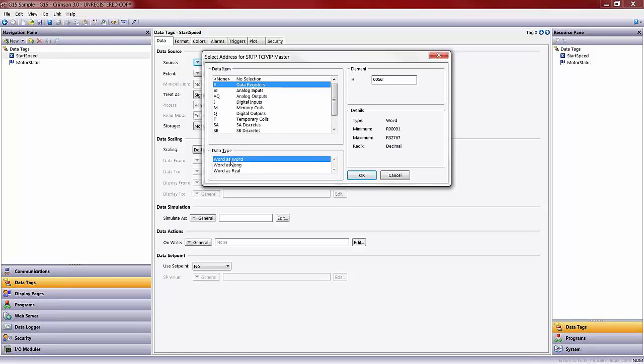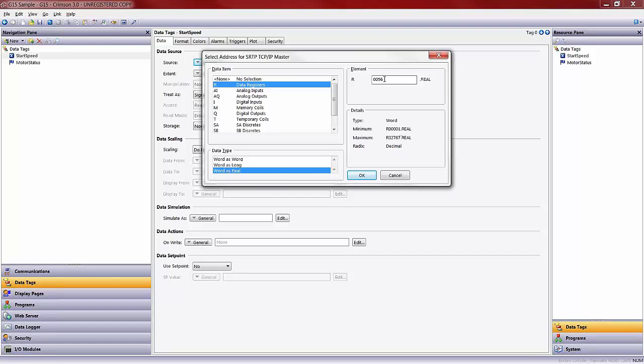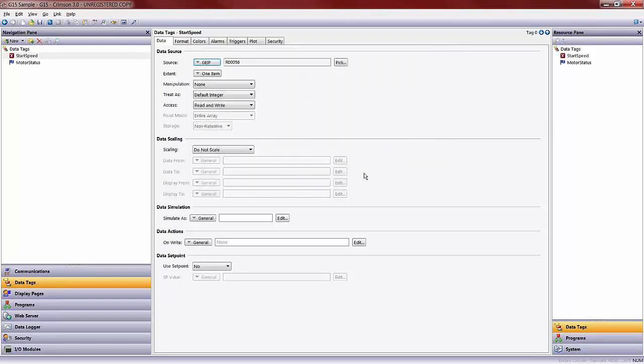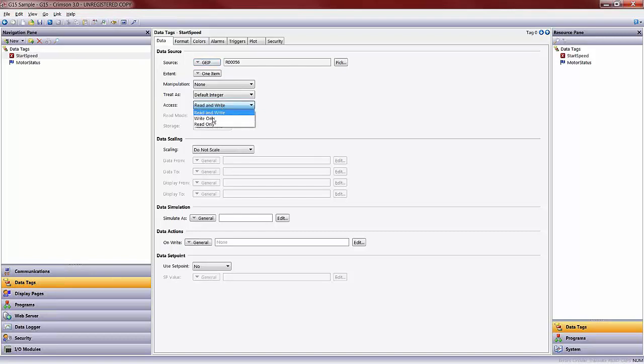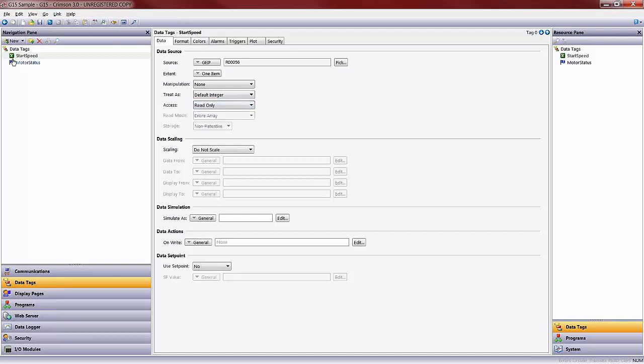Word as word would mean that it's an integer or a word. If I did word as real, this would make this a floating point of some sort, and would in fact bring over percent R, 56, and 57. I'm going to do word as word. It's a single integer value as a set point. The red indication now means that I can read and write to my percent R, 56 in this case, within the GE controller. If I were to change this to a write only, it would remain red, and if I were to change this to a read only, this would change to be green. That's the color indication noted here. I'm going to leave this as a read and write capable tag, so I'll leave it as a red indication.